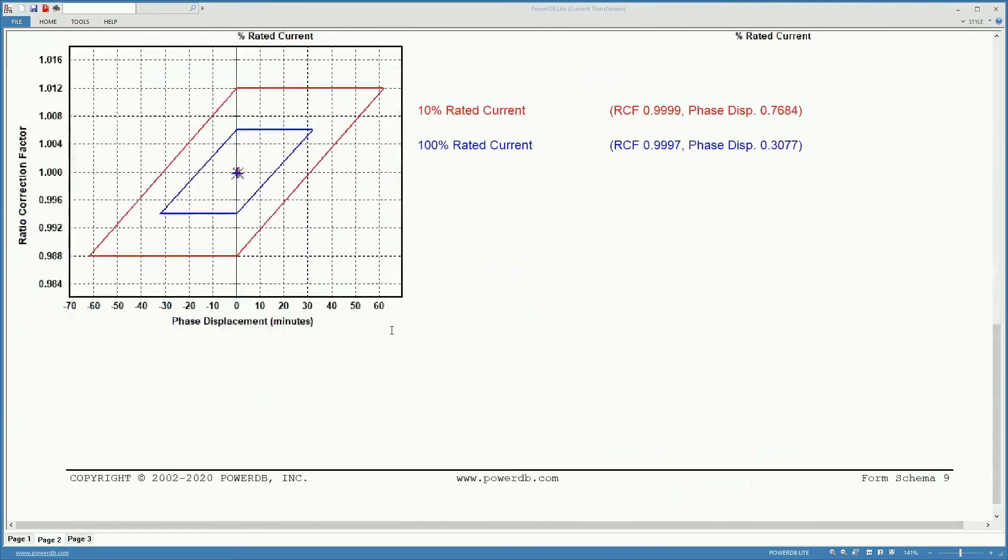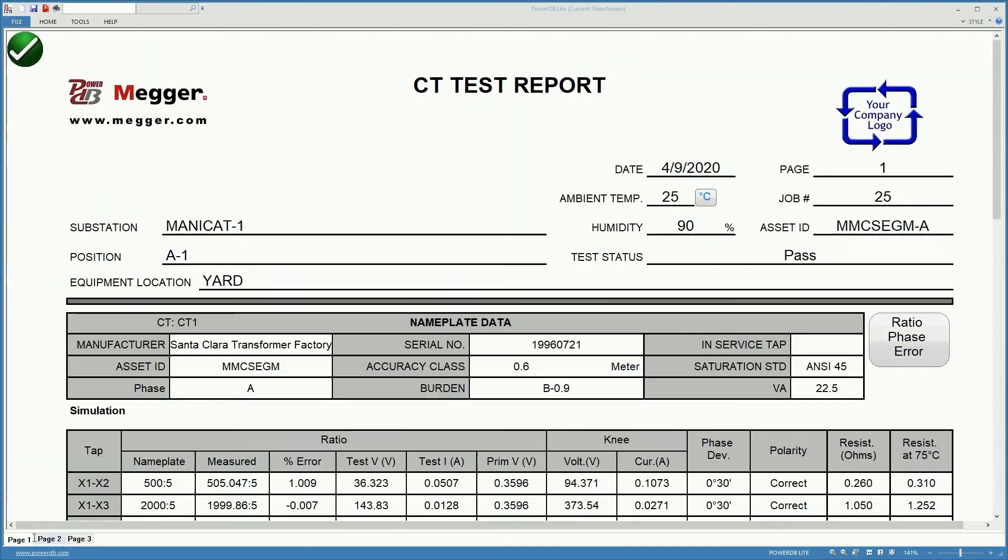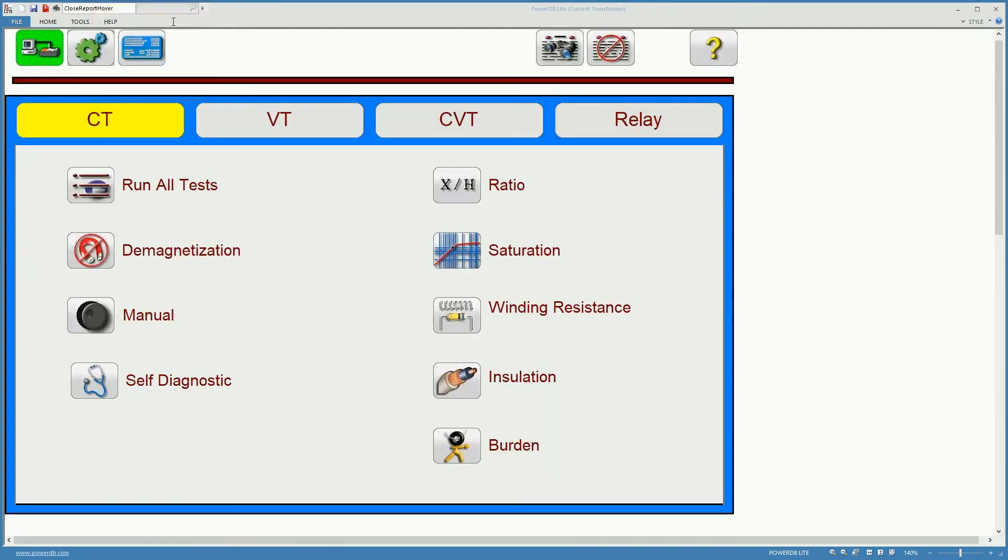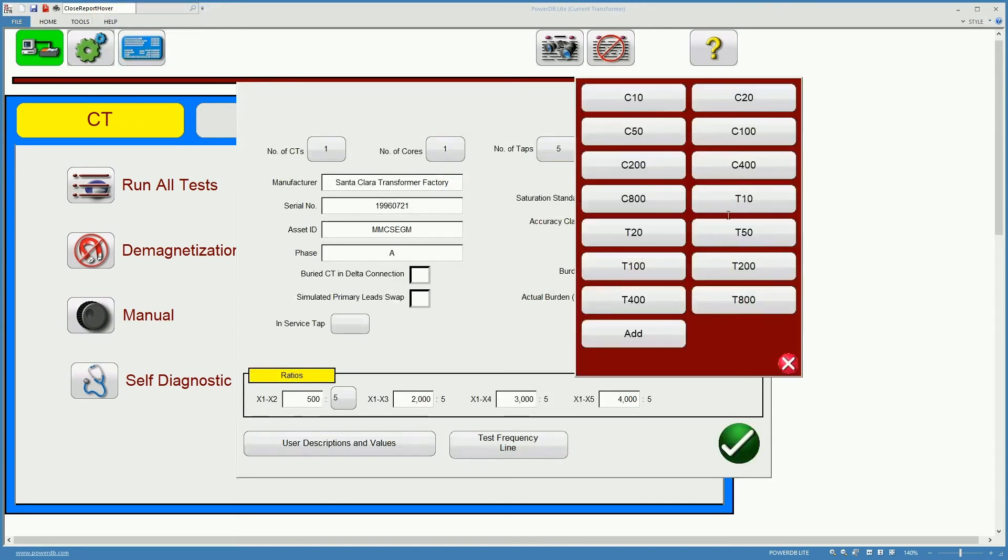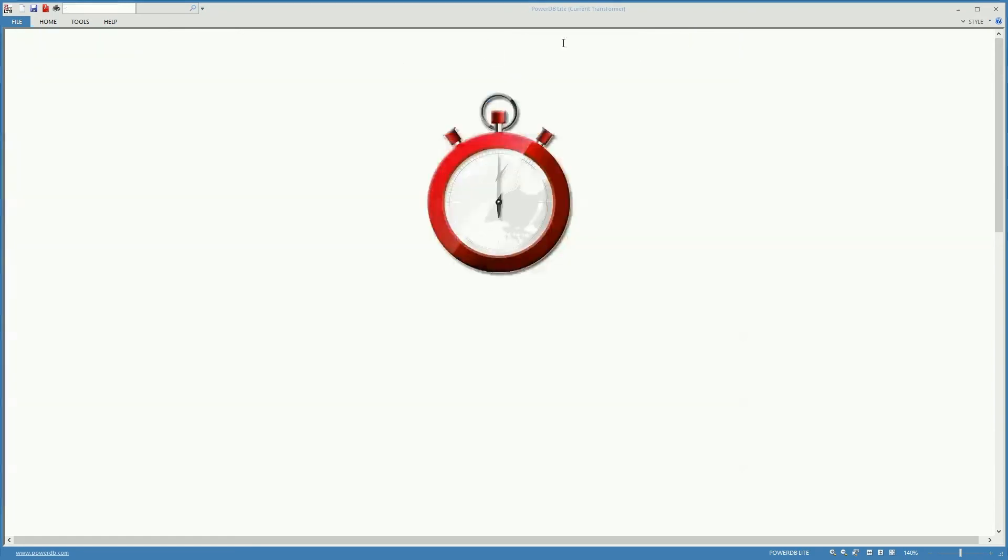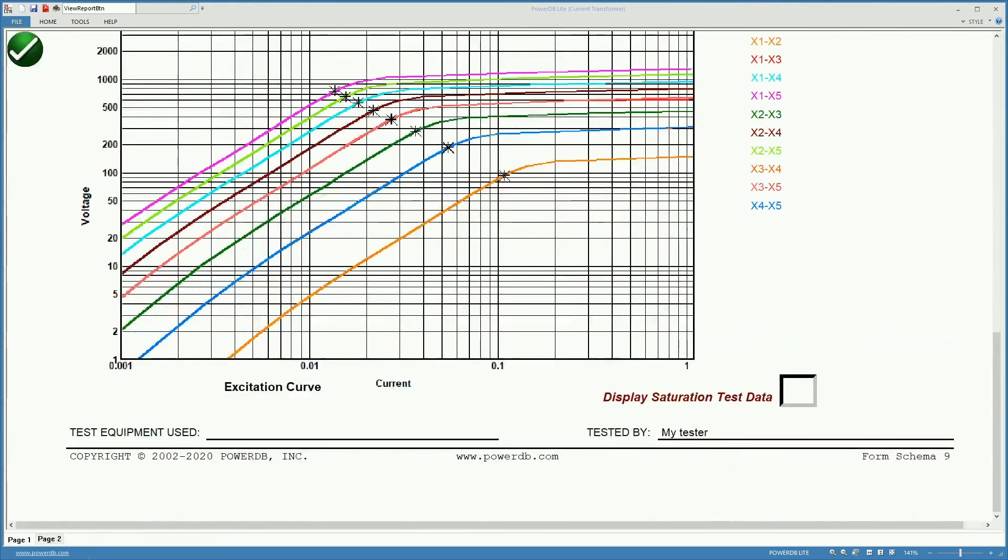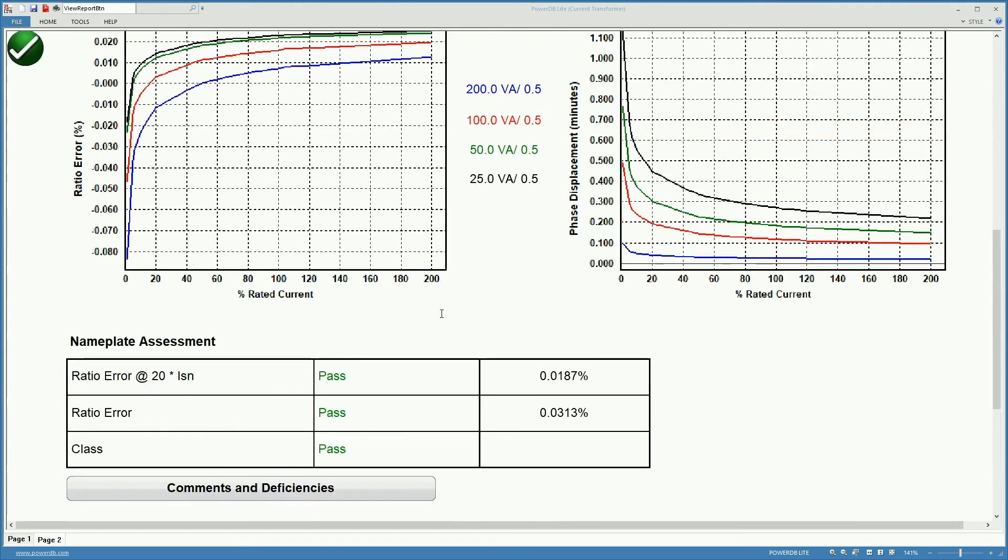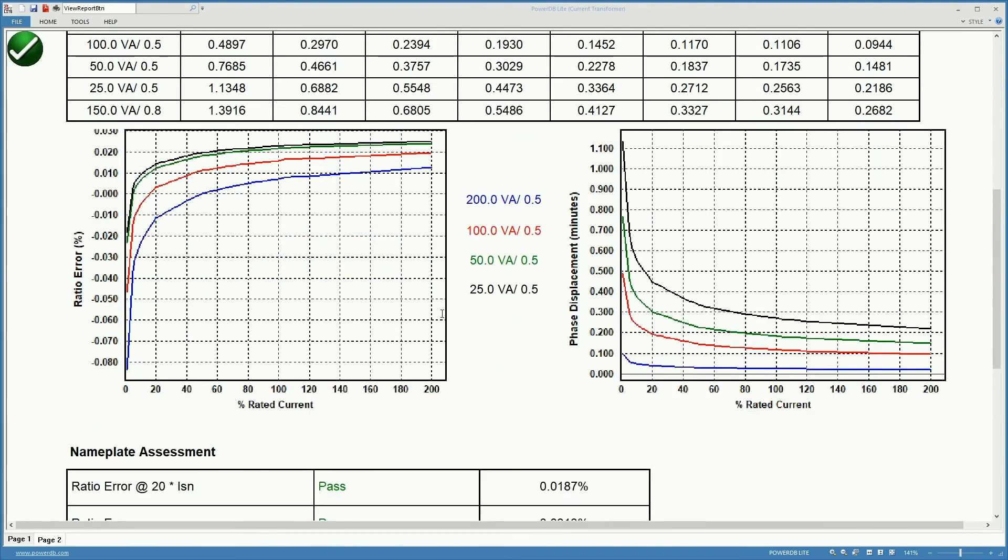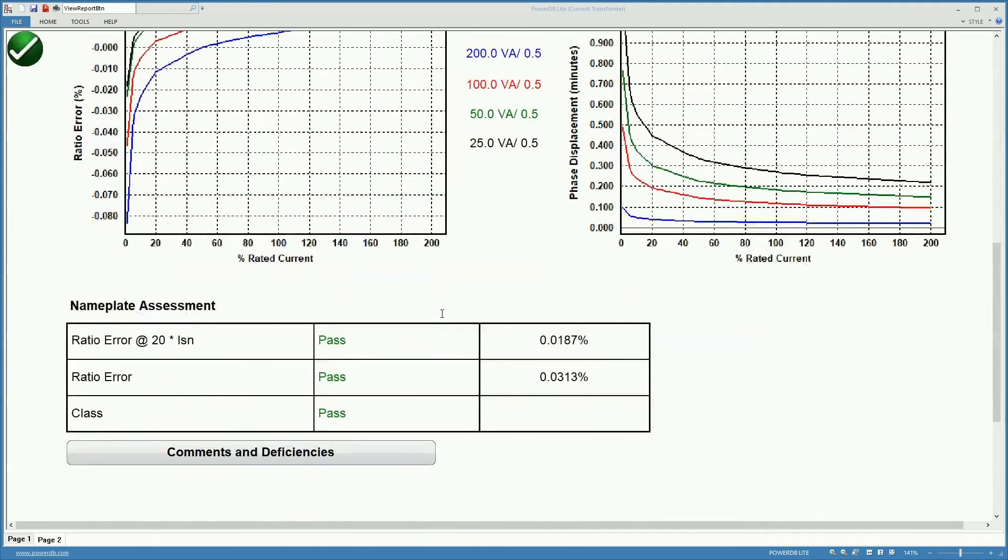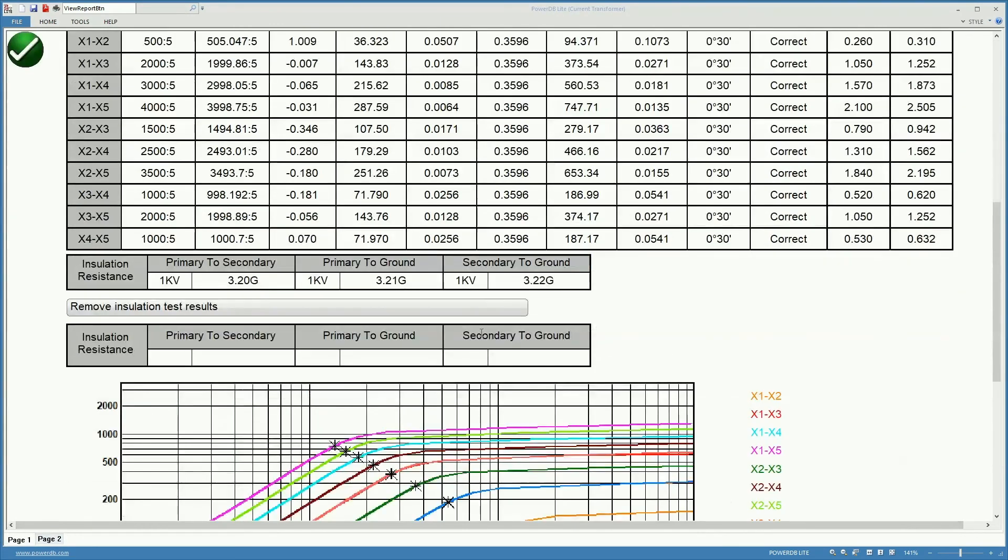If we classify the CT not as a metering CT but as a protection CT, we will see that the ANSI parallelogram will disappear, since that parallelogram is only relevant for metering type CT. So when you have a combined type and you want that parallelogram to show up, you have to classify it as metered, put there the metering classification of the CT.